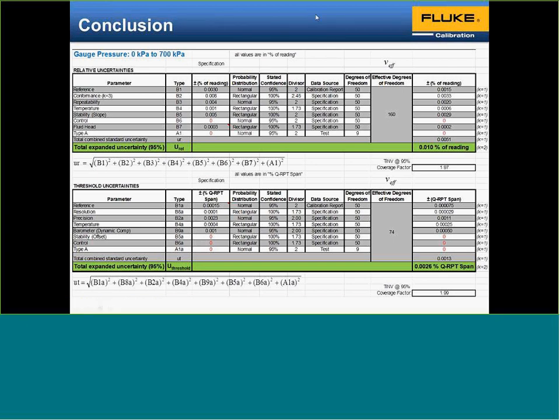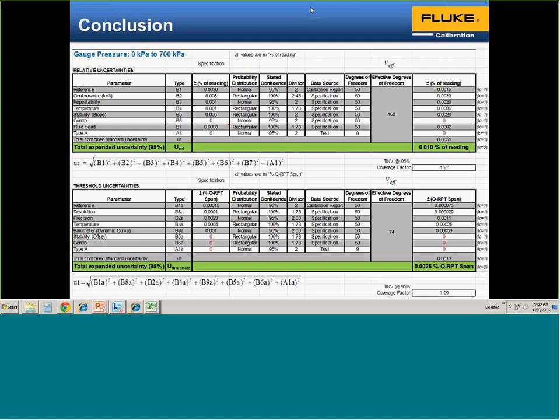Here's one that's more deadweight tester related. For a deadweight tester, what resolution do we need to take? For those that aren't as familiar with the product, it's one where pressure is determined by a floating piston with a force applied to it, so it's force divided by area. The pressure is calculated from the force created by the masses divided by the effective area of the piston. So resolution doesn't really play into it as much. You have terms of sensitivity, which is basically looking at the smallest mass that you can apply to the tester and have a change in the output of the deadweight tester.